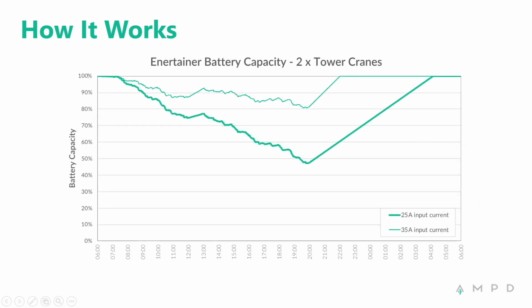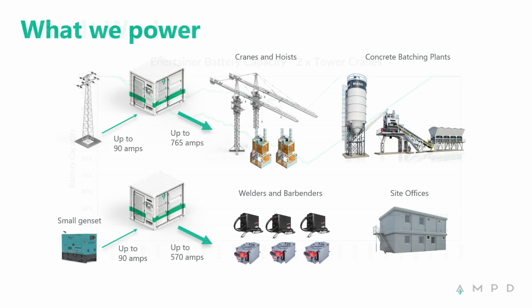This is an example of one of our units powering 2 cranes. Those 2 cranes would usually require 2 300 kVA generators, about 600 amps of power. We can use 1 battery for those 2 cranes. If you use a 25 amp input that would usually require 600 amps, you barely go below 50% of battery capacity. With a 35 amp input, you barely go below 80% of capacity. So essentially you can run all day. If the power completely goes, you can run the site usually for a day and a half, which is usually enough time for power to come back up.